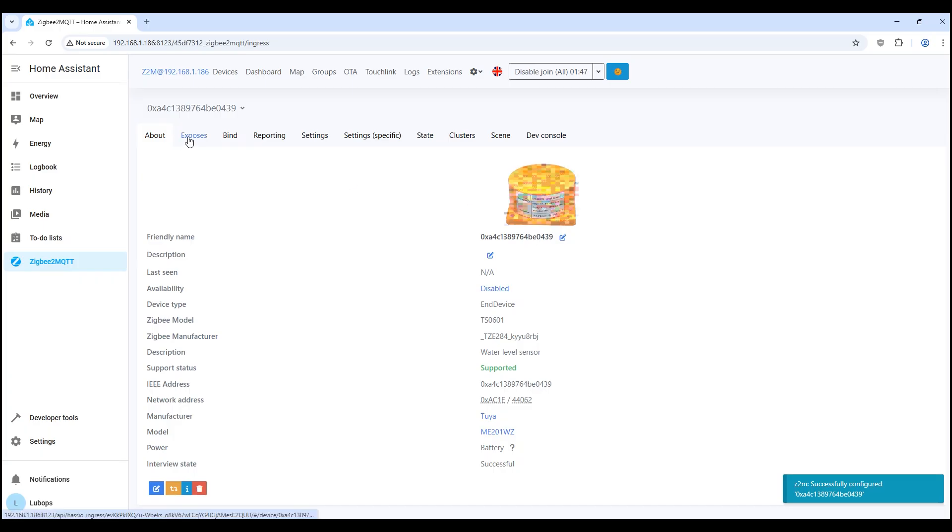What the sensor shows: liquid depth 4.94 meters. This is the current liquid depth that the sensor sees from the set tank depth level. As we have already seen with the application settings, it counts from the specified height value. Liquid level percent null. But this is the percentage of filling, but it is null now because the base is not set. The sensor does not know how much is considered full. We configure this a little lower. Liquid state also null. The level state is normal, small, large, but without specified boundaries it cannot calculate it. This is also fixable.